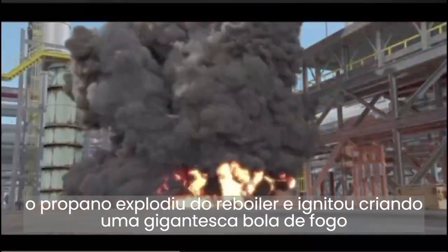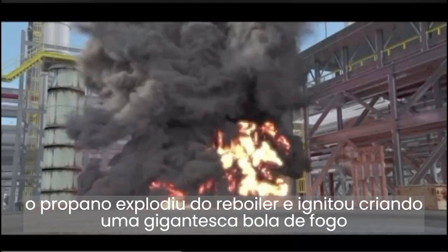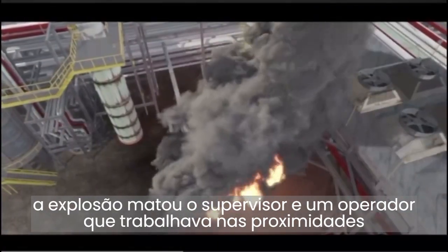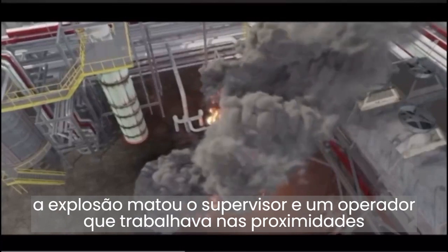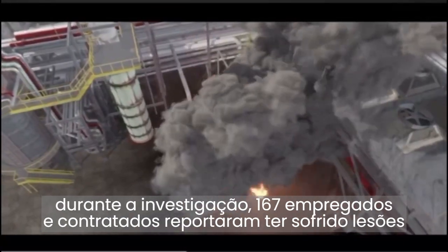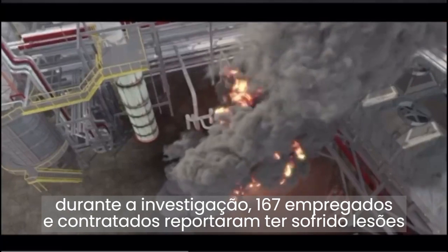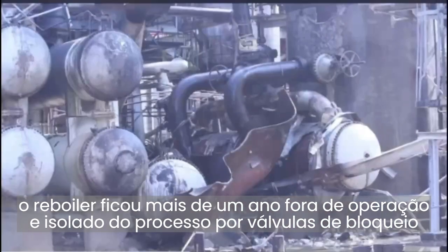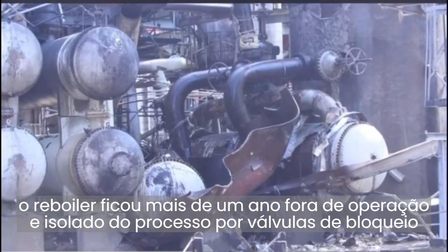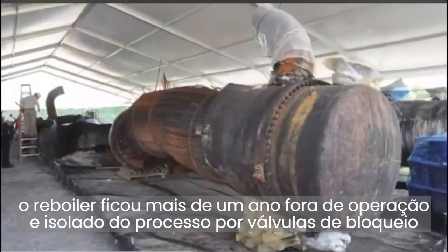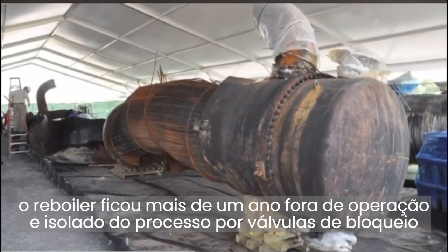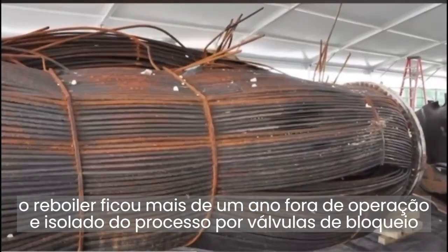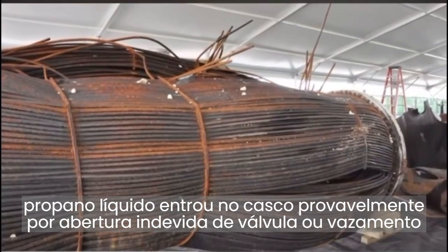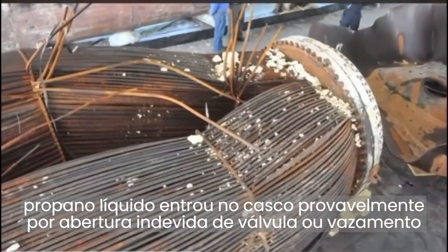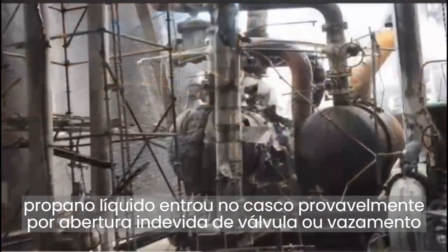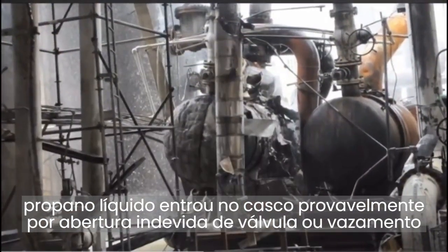Propane exploded from the reboiler and ignited to create a massive fireball. The explosion killed the operations supervisor and an operator working nearby. 167 Williams employees and contractors reported being injured. During its investigation, the CSB found that prior to the explosion, the standby reboiler had been out of service for over a year, isolated from the process by closed block valves. But during this 16-month period, liquid propane unintentionally entered the shell of the reboiler, perhaps through a mistakenly opened valve or a leaking block valve.